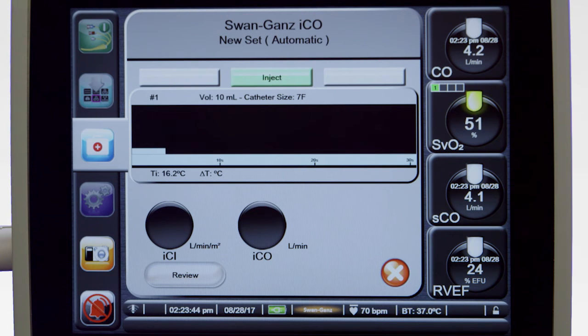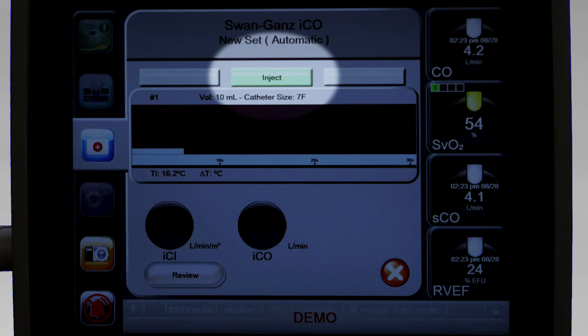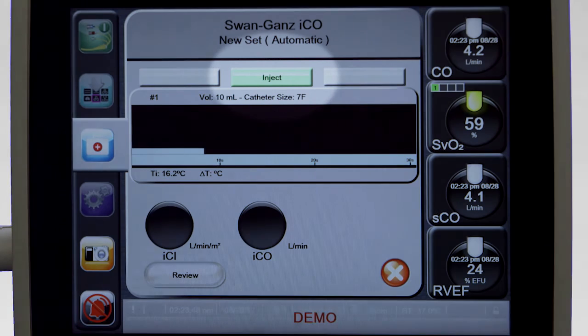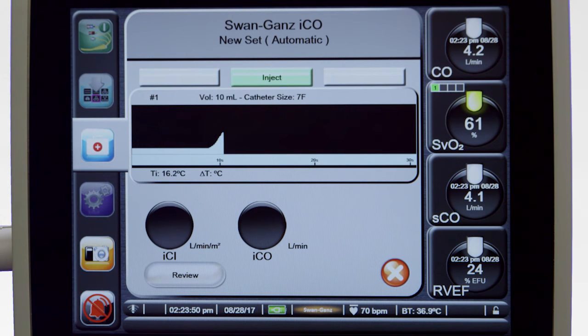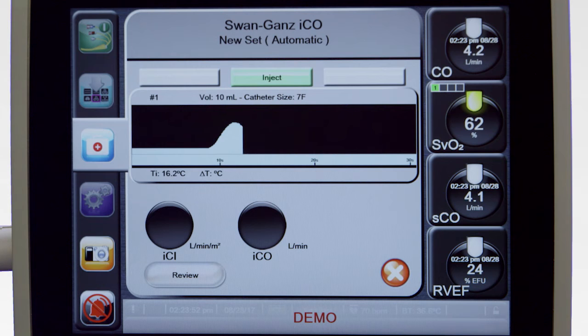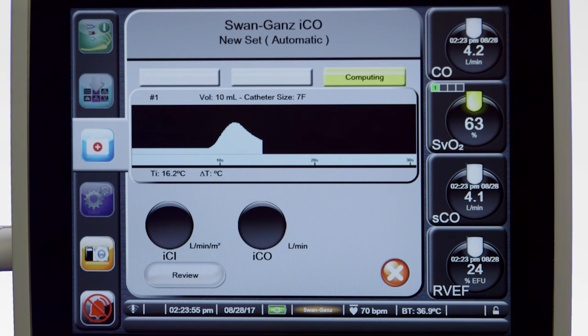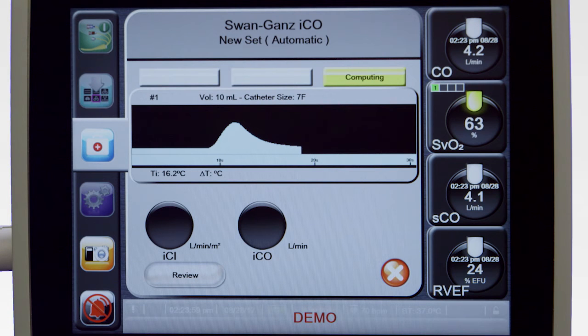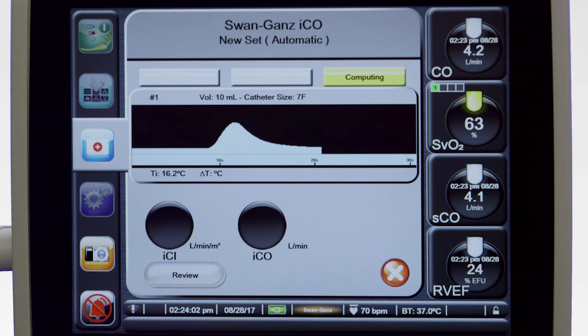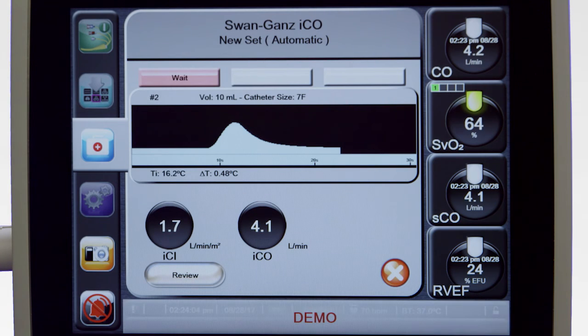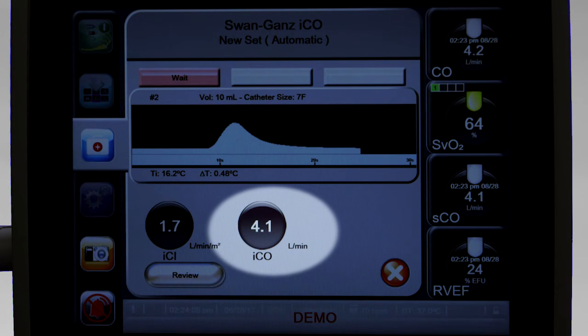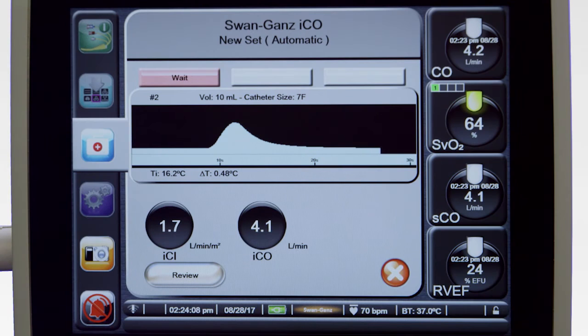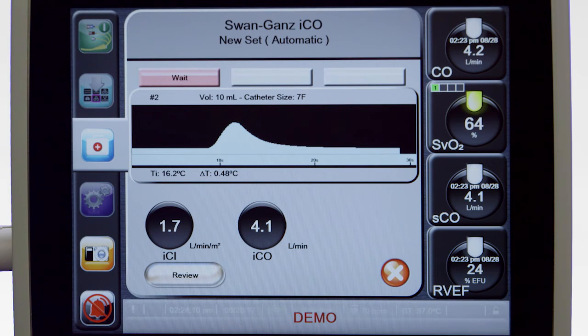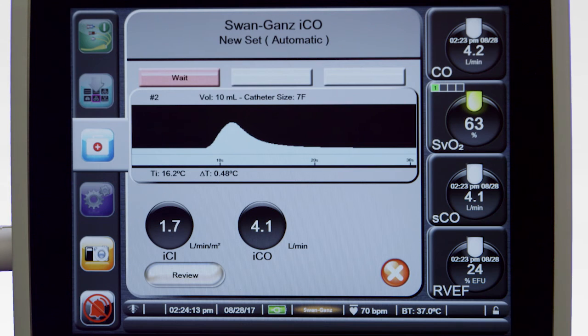If you have selected Auto for the bolus mode, you must wait for the green Inject icon to appear. Once it appears, you may inject your first bolus. If you have selected Manual for the bolus mode, then you must touch the Inject icon when you are ready to inject the bolus. Once a bolus is injected, Computing will highlight on the screen, and the resultant ICO measurement will be displayed. Repeat this procedure up to 6 times as desired to obtain a sufficient number of readings to produce a good average value.